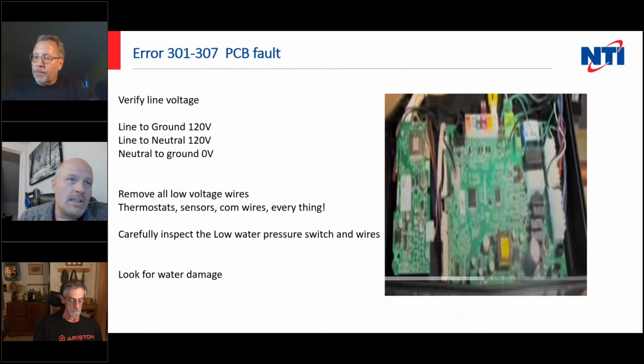Second thing you want to do, remove any and all low voltage wiring. Get rid of the thermostats, the tank sensors, the system sensors, anything that's got a low voltage that's connected to the boiler, remove them all. And you're doing this to simplify the situation. If your problem goes away when you remove all that stuff, I would say the odds are better than average that your problem lies in the system wiring.